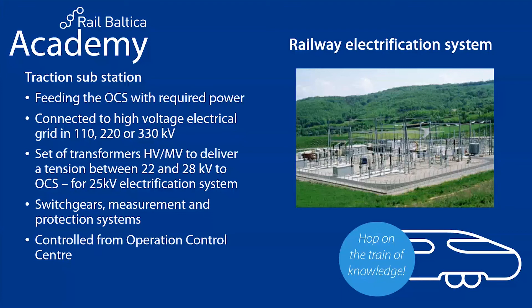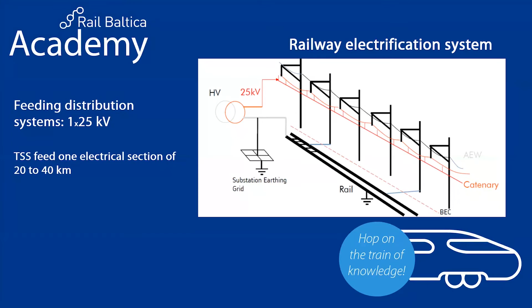The feeding distribution systems: we have different ones. In 25 kilovolt traction, the first one is called 1x25 kilovolt. This is a simple system, where one traction substation feeds one electrical section of 20 to 40 kilometers, depending on traffic. This is composed of a simple catenary with AEW and BEC, which are grounding cables. The OCS is simply connected to the substation at 25 kilovolt, and the ground is connected to the rail traction return current.